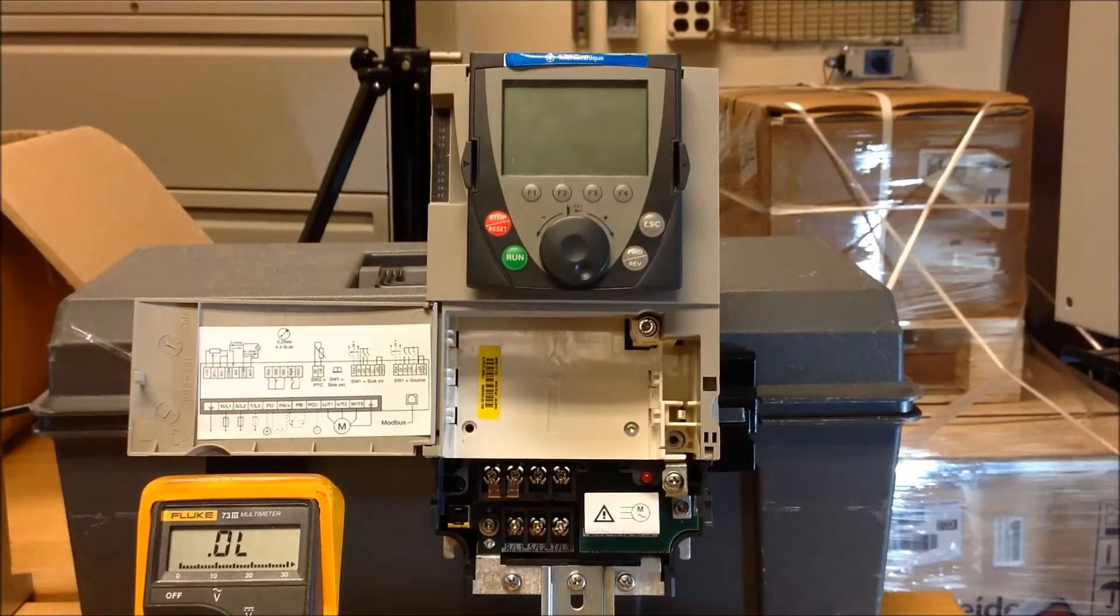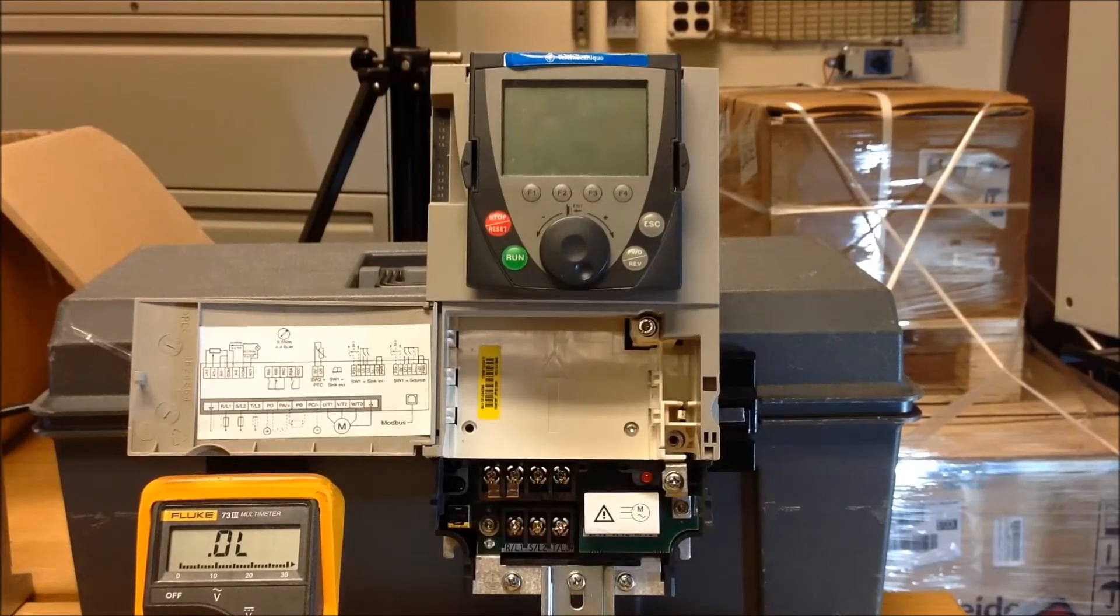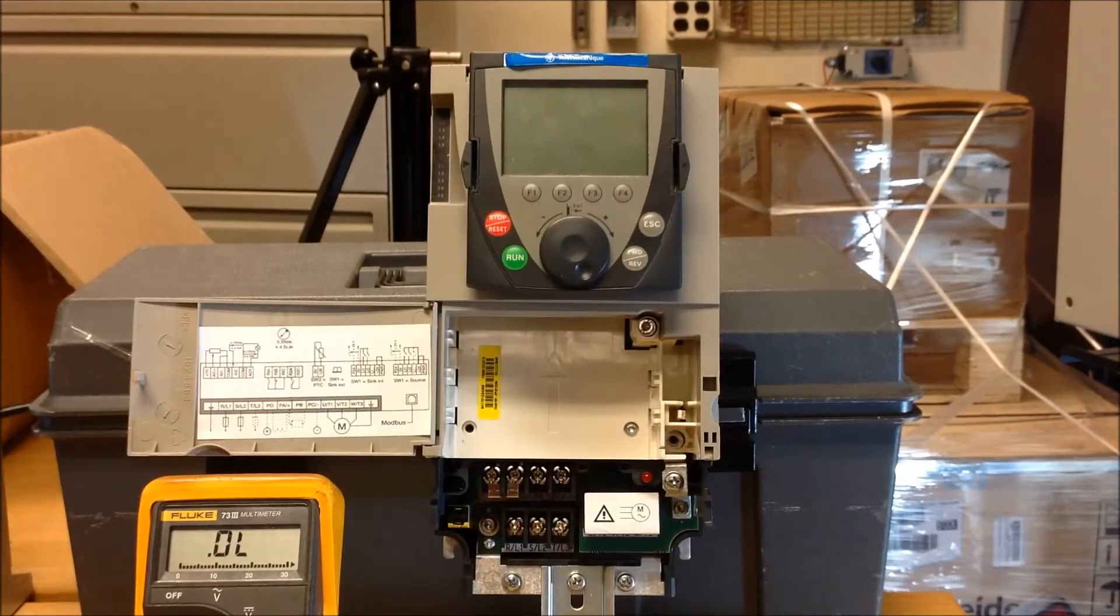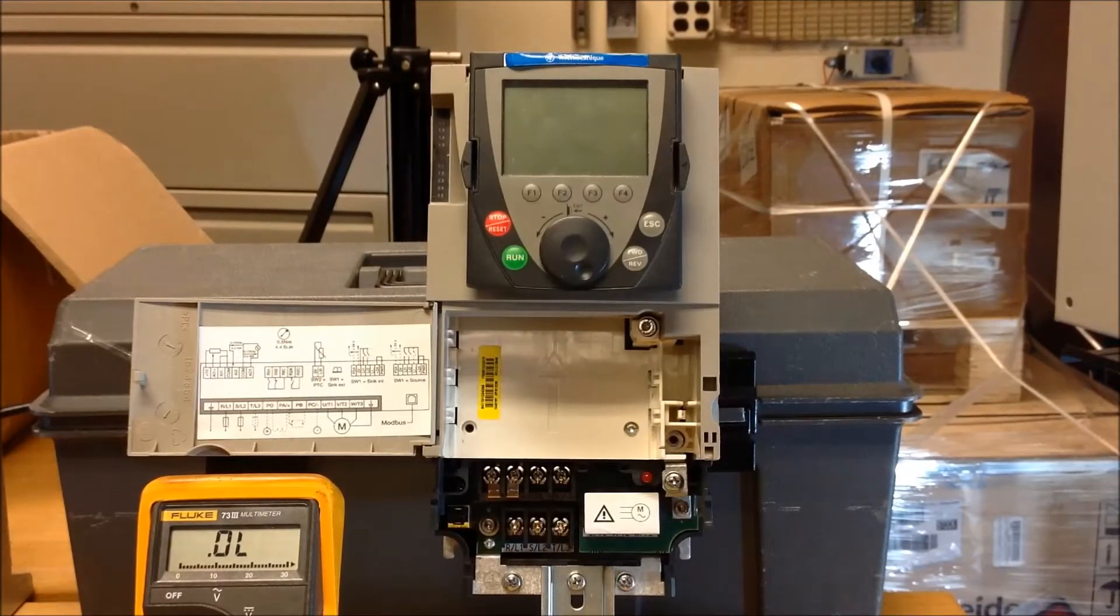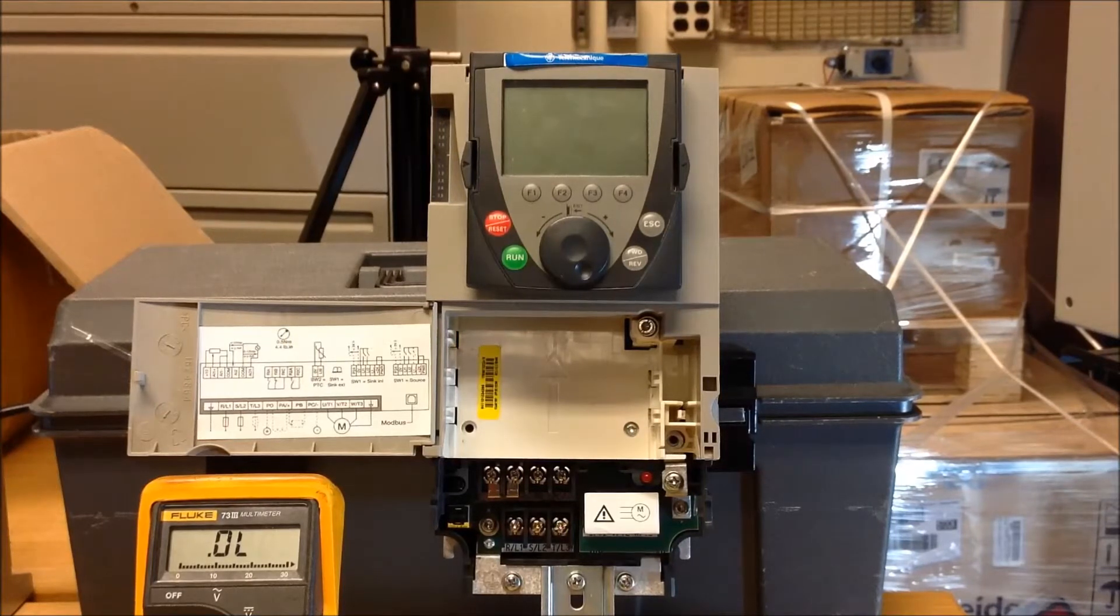and to check the output side of the drive, instead of the input this time, you go between your T-leads, T1, 2, and 3, to the DC bus, PA and PC.